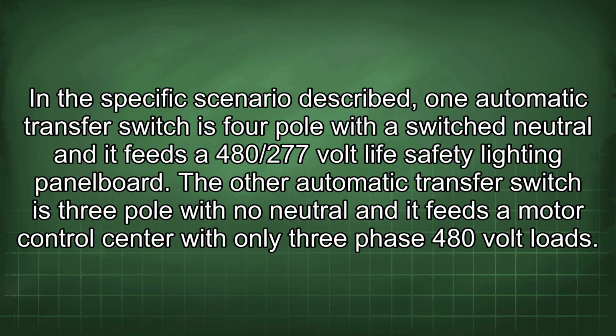In the specific scenario described, one automatic transfer switch is 4-pole with a switched neutral and it feeds a 480/277 volt life safety lighting panelboard. The other automatic transfer switch is 3-pole with no neutral and it feeds a motor control center with only 3-phase 480 volt loads.